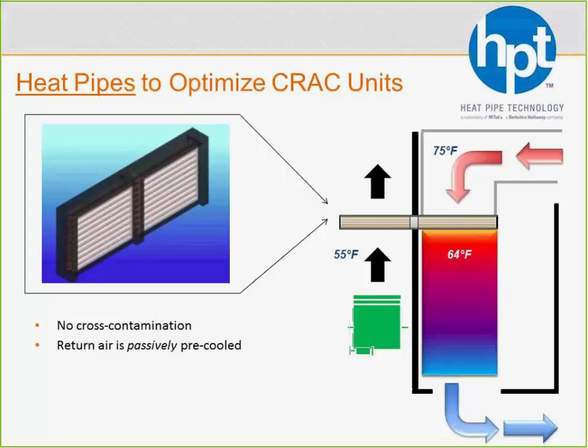We also, again, don't need any power. The only power you're adding is this fan. You've got to have some kind of fan blowing air across the heat pipe, but you'd have to have that on any device that you use. So for the heat pipe, we don't need a motor or a pump or anything to work. So we're passively cooling it, which means that it's about as minimum maintenance as you get while getting heat recovery in a data center. And that's obviously a benefit for all these data centers out there. The less they have to go out there and maintain them, the better.